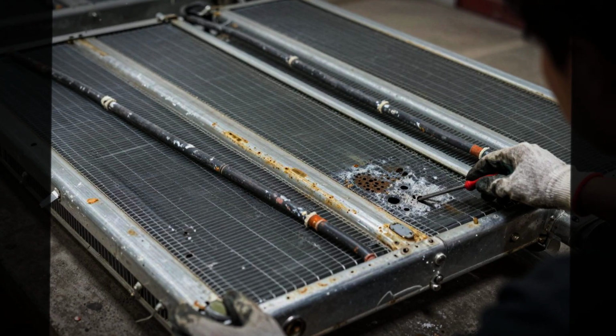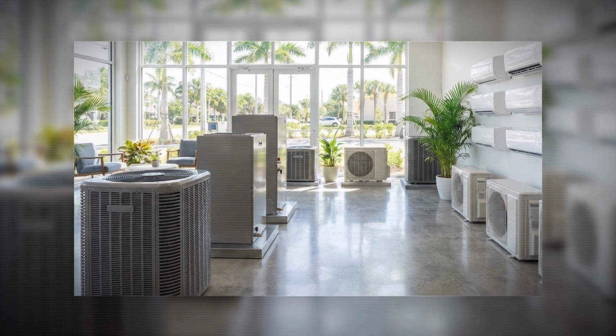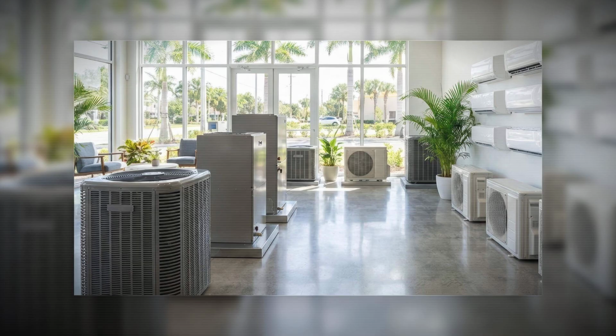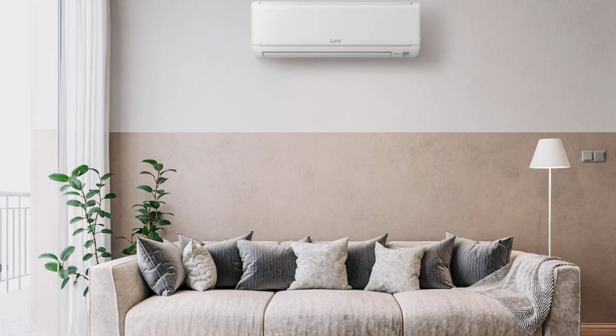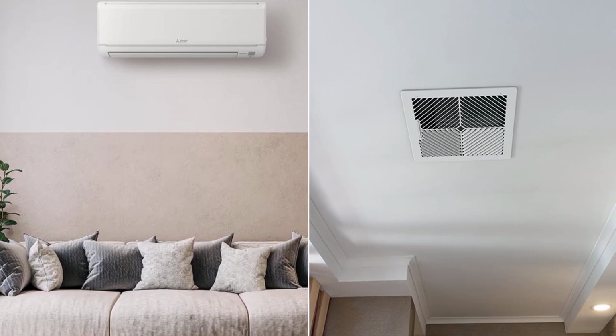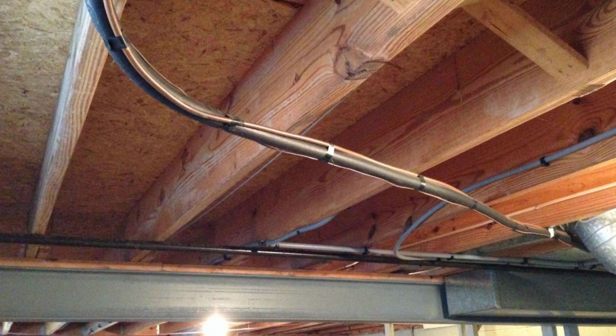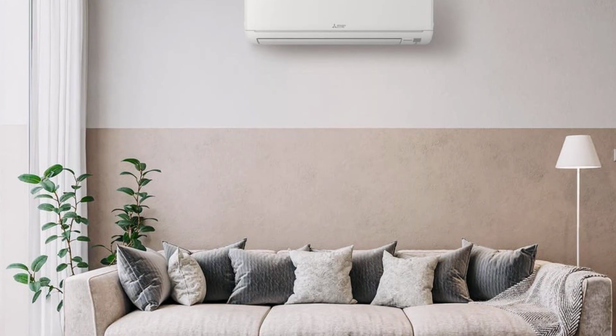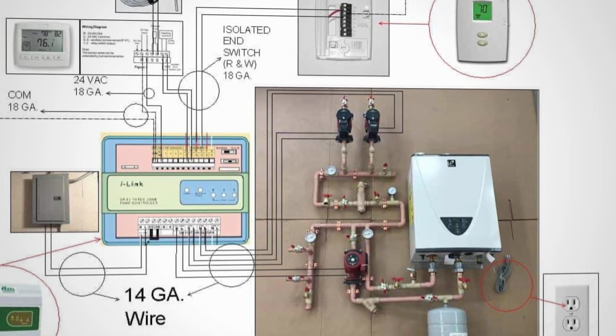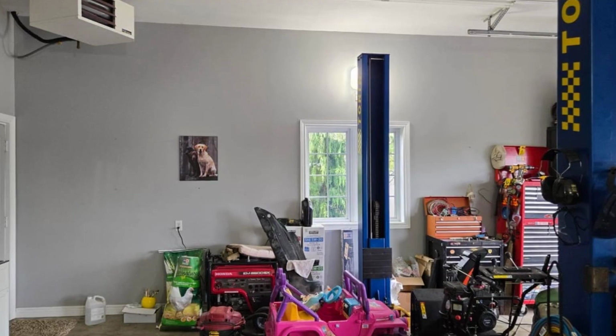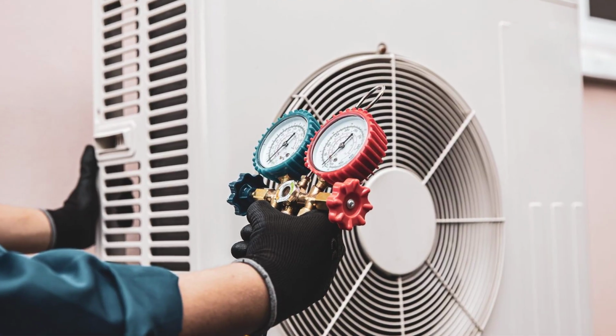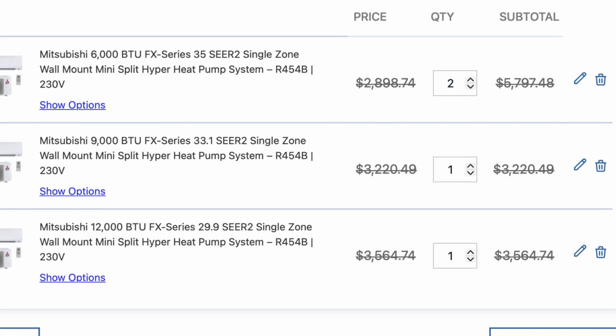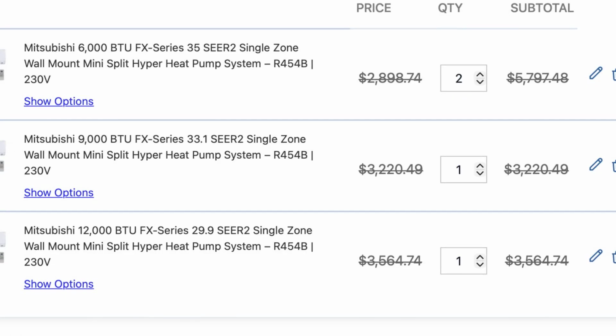This is not a promise of immortality. No coating lasts forever, but it is a signal that the manufacturer is at least acknowledging the coil environment durability reality up front, instead of hoping you never search aluminum corrosion HVAC problems until after the warranty expires. Trade-off: ductless is a different installation model than traditional ducted systems. Line set routing and quality matters significantly. Whole home conditioning may require multiple indoor heads or a different multi-zone product family with higher complexity. But for targeted applications where you want proven corrosion resistance from a manufacturer willing to talk about it, Mitsubishi's coating story is worth the dealer conversation.